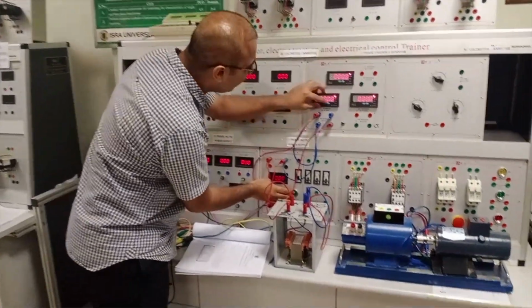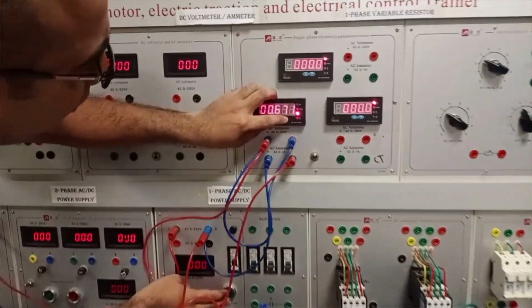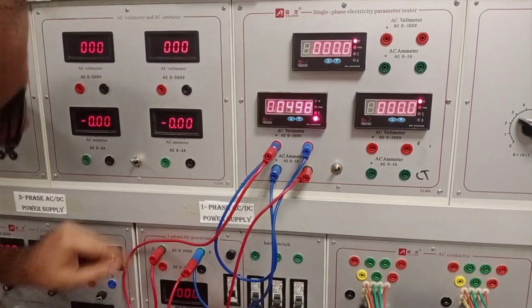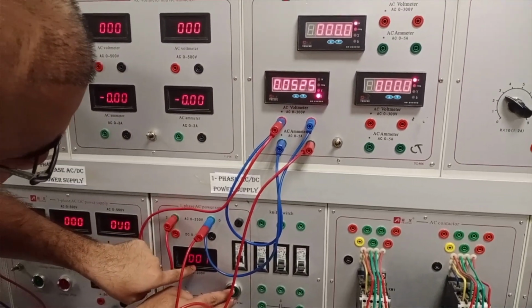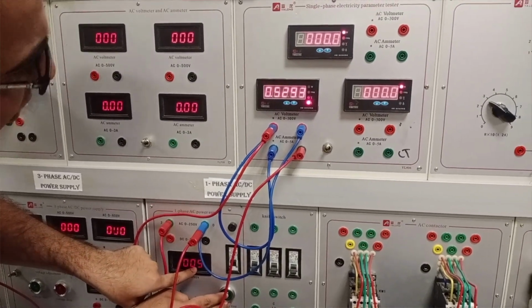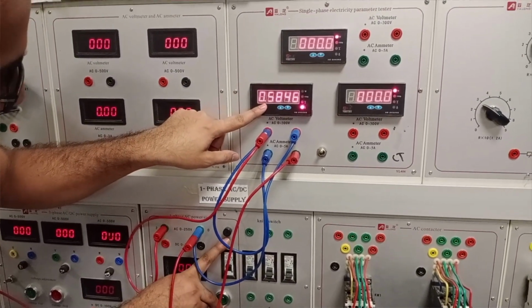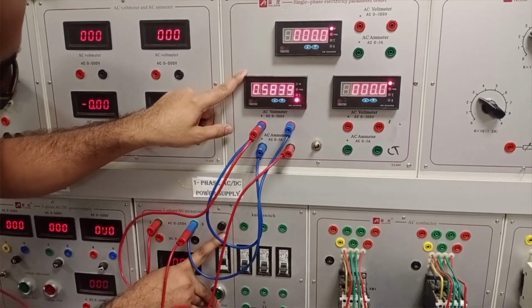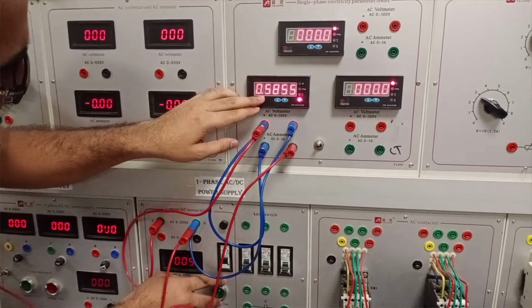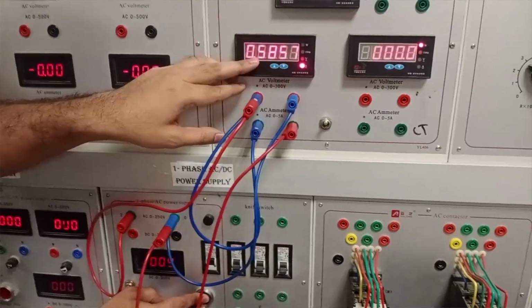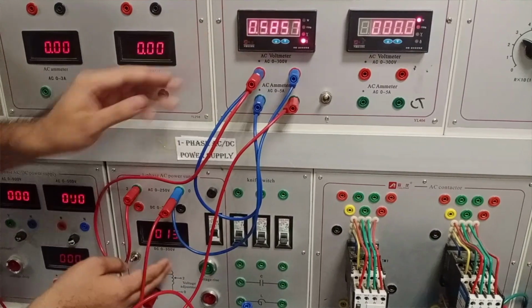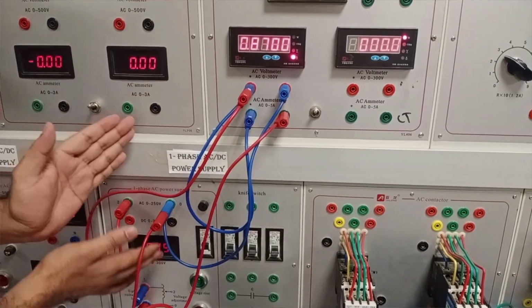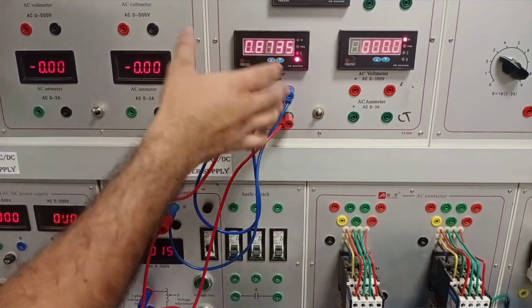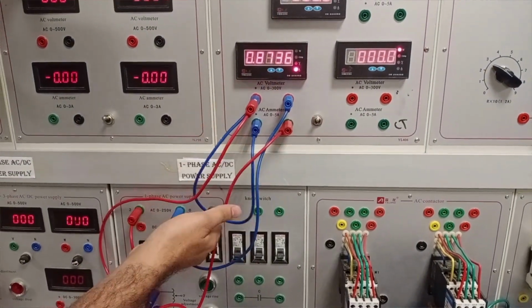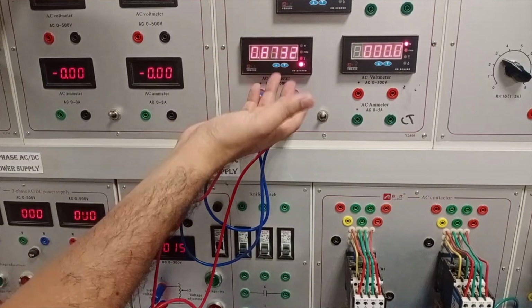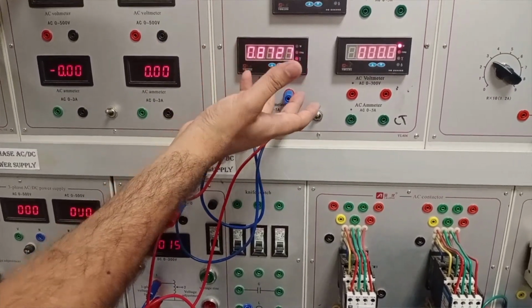So you can see this wattmeter is placed on this, and we are going to increase the voltage. Up to 9 volt, a 1 ampere fuse has been installed in this cap. So 0.58 is the current which is flowing.